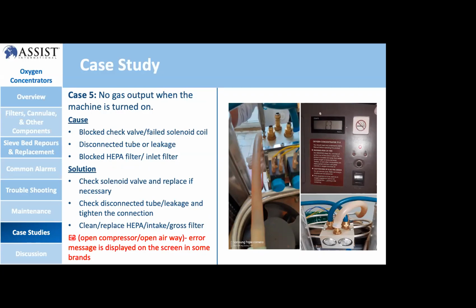The cause for this problem, we identified the cause as a blocked check valve. That means we have a solenoid valve which delivers compressed gas to the sieve beds. So we get a failed solenoid valve and disconnected tube or leakage. That means if there is a leakage or disconnected tube, the gas is not delivered to the patient. A blocked HEPA filter or bacterial filter, or total blockage of the inlet or compressor inlet filter, cause these problems. That means the machine is turned on, it is functioning, it is running, but there's no gas at output. Those causes normally leave the machine out of work.